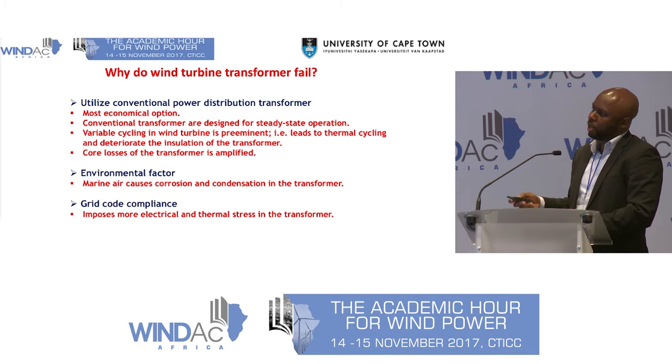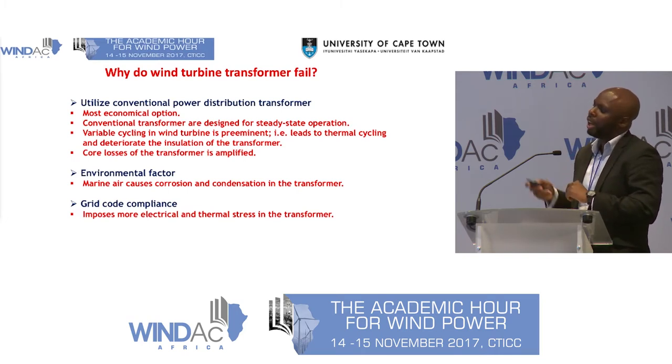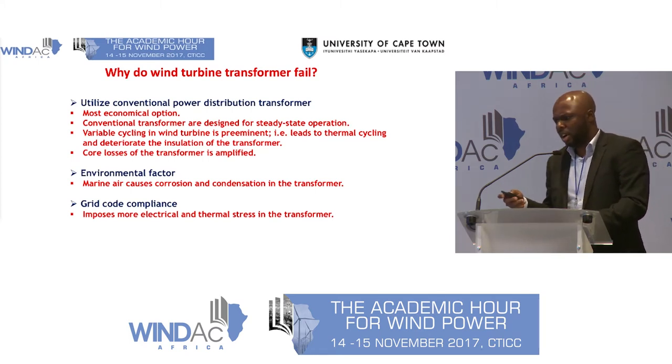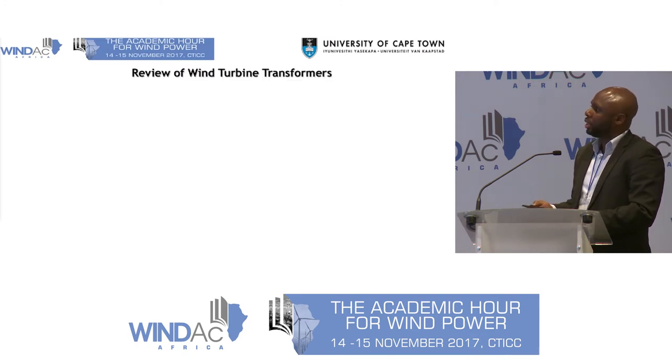Now, when that happens, because of the sudden drop in voltage of the grid energy, you have magnetic flux deviation in the grid side of the transformer. And because the magnetic flux deviation decays slowly, it leads to inrush of current in the transformer itself. And by that, you have a lot of electrical stress, and it exerts some axial forces on the transformer, also further degrading the insulation.